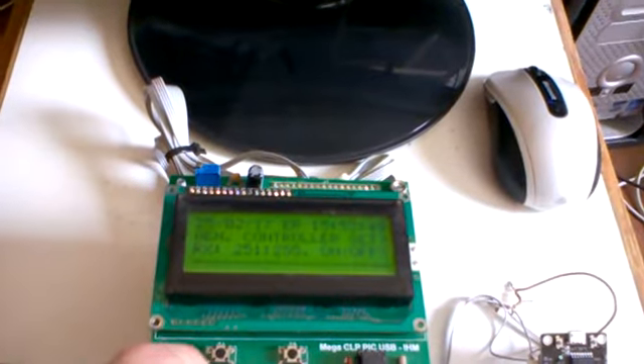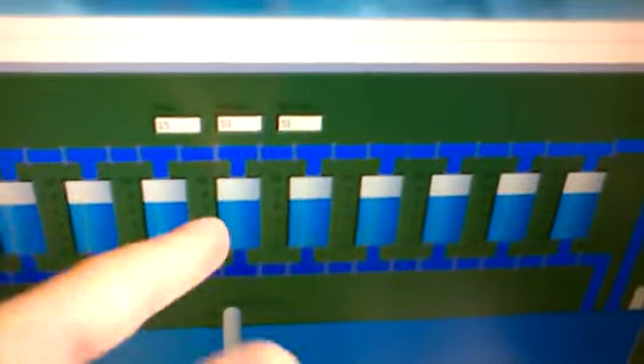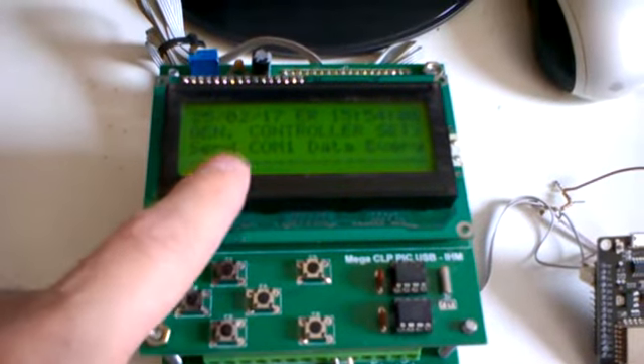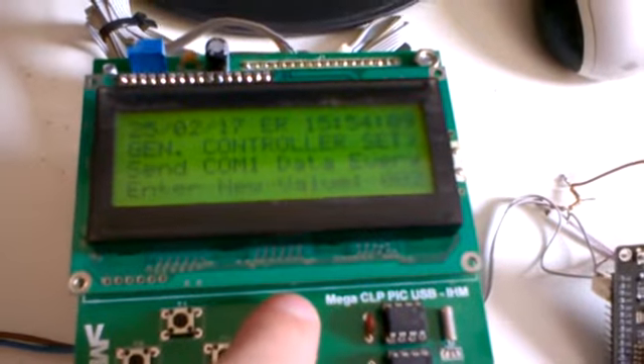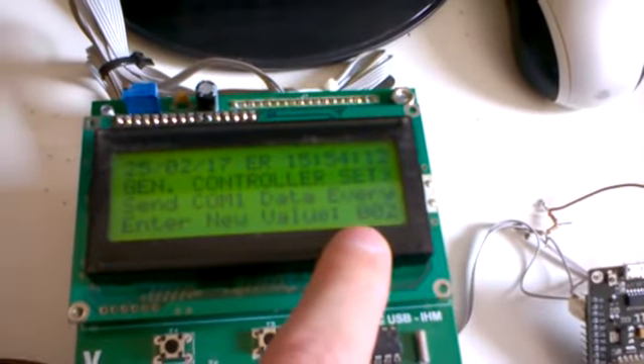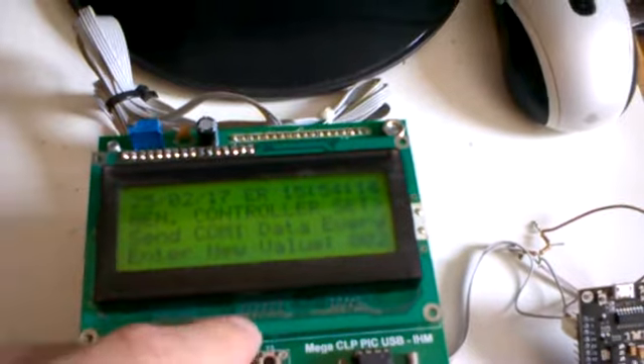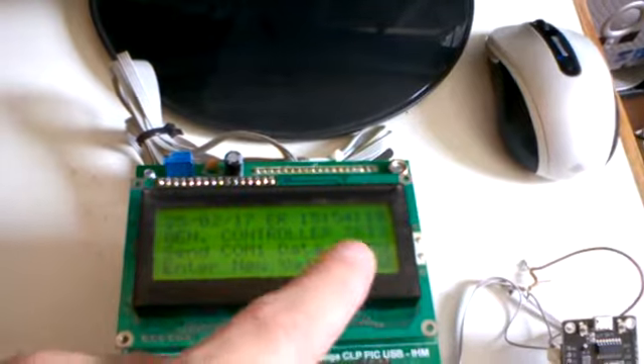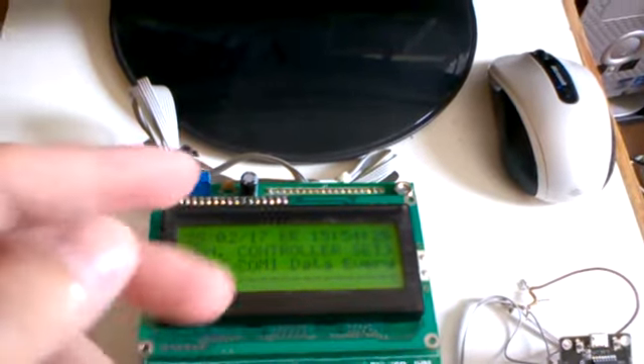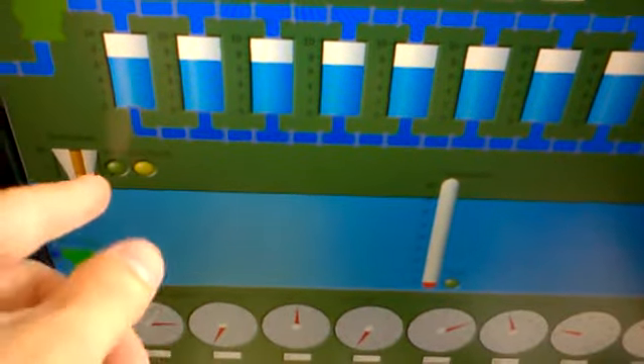So it takes a couple seconds between the supervisory sending the command and actually being able to execute and turn on the actual load. Right now, by the way, the refresh rate right now that I'm using for this supervisory is actually two seconds as you guys can see here on the timestamp. This refresh rate is controlled over the controller. I can actually set it up over here. So it's a great thing. I can actually set it on the controller and the supervisory will work at the same refresh rate. So at this particular refresh rate it takes eight seconds between I turn on, I send the command, and actually be able to see here that the automatic feeder was turned on.